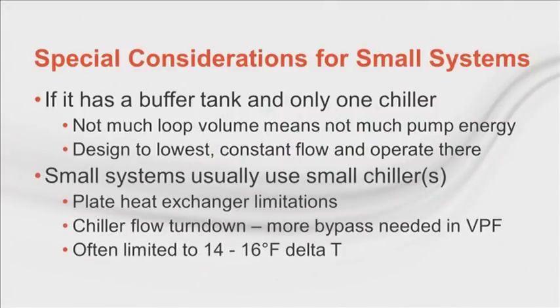This brings us to limitations of smaller, more packaged chillers. Unless the manufacturer has specifically designed it for variable flow, for example by having 3 pass options, you may end up with a variable flow system that has very little flow turned down. It's also more difficult on some chiller designs to select for a higher DeltaT. Brazed plate heat exchangers have performance degradations that can make more than 14 or 16 degree DeltaT impractical. Keep this in mind when optimizing the coil selection or reselection, or find a smaller chiller with a different style of heat exchanger. Another method is to put the chillers in series with each other, or with something like chilled water or ice storage. Susanna brought up an interesting point.